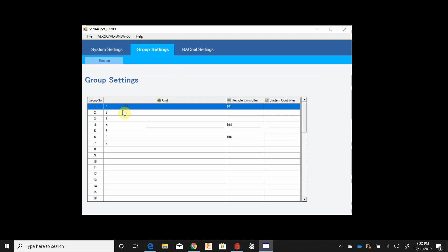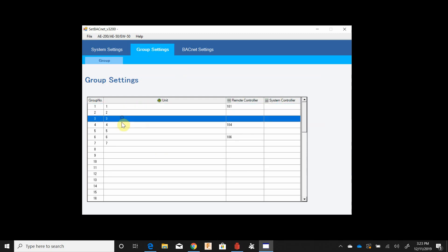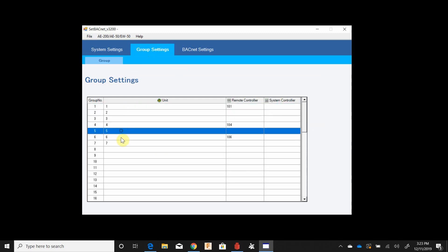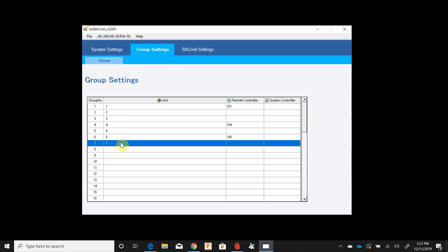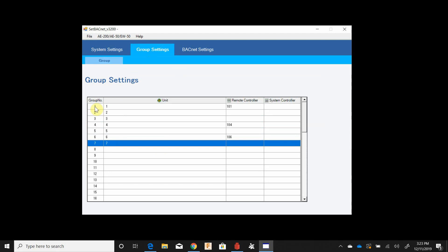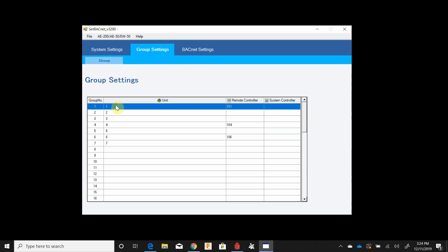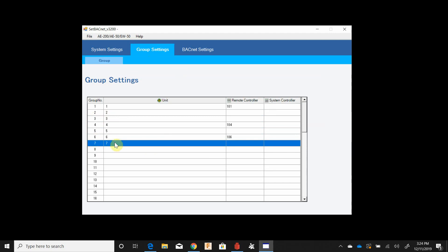Our group settings shows what our units are and where they're connected. This can also be a handy cross-reference for the system integrator because this unit number here is going to be what MNET address or addresses are associated with the group. In this case I've kept the MNET address and the group address the same, but there can be situations where these can be flip-flopped. This is set ahead of time in the initial settings tool. Once that's loaded here, we'll actually have some units to look at for the BACnet settings.